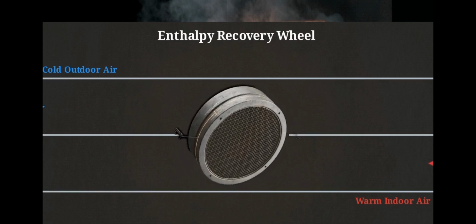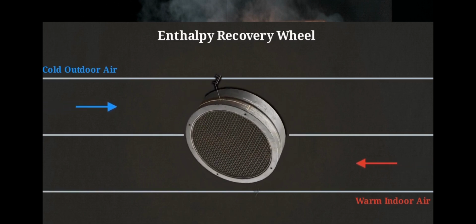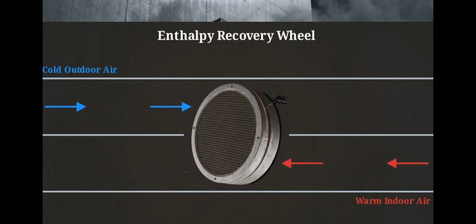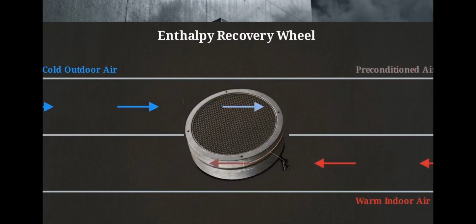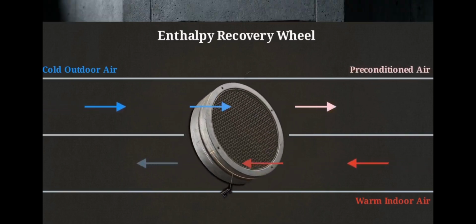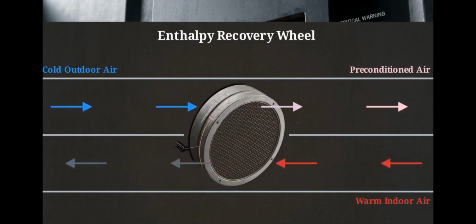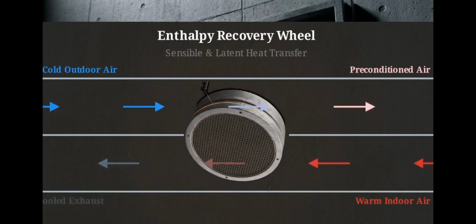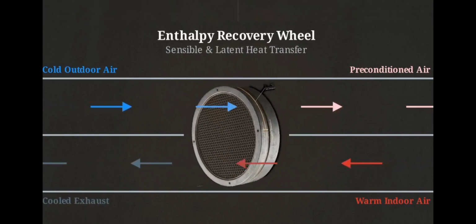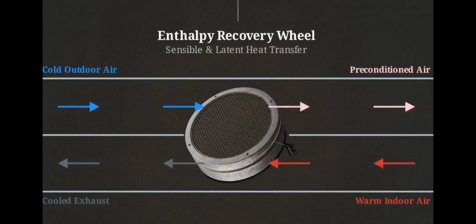This spinning matrix sits right where your indoor and outdoor air streams cross. As the warm indoor air gets pushed out, the wheel steals its heat and moisture. Then, it spins and transfers that energy directly into the incoming cold outdoor air, preconditioning the air for free. Maximum fresh air, minimum wasted energy.